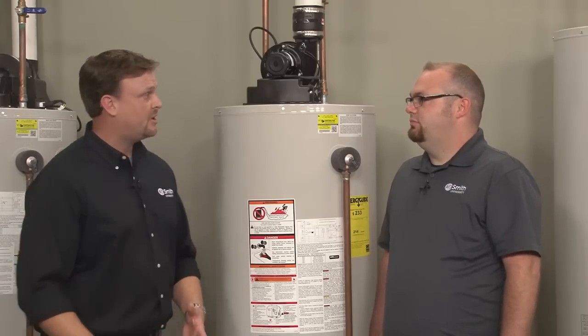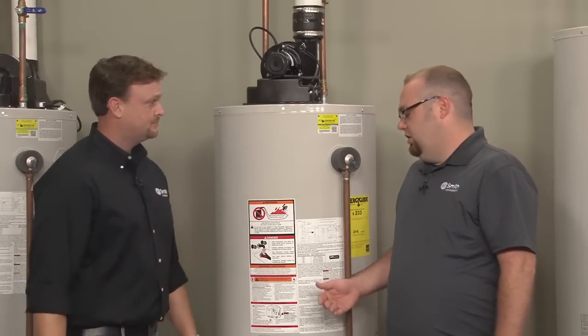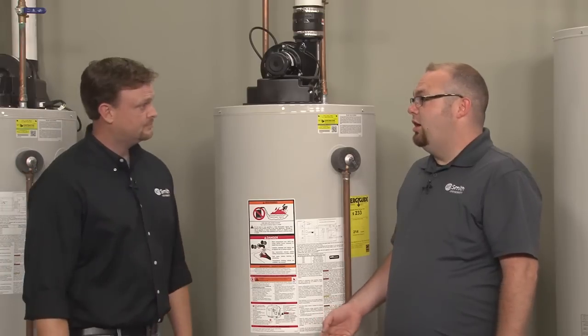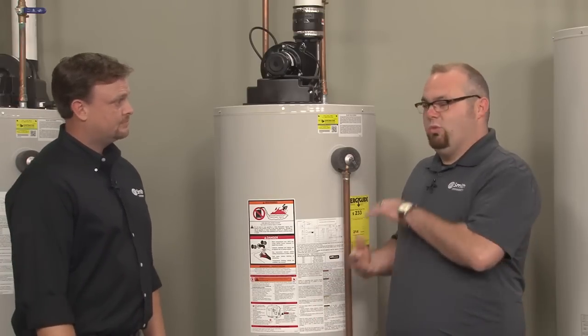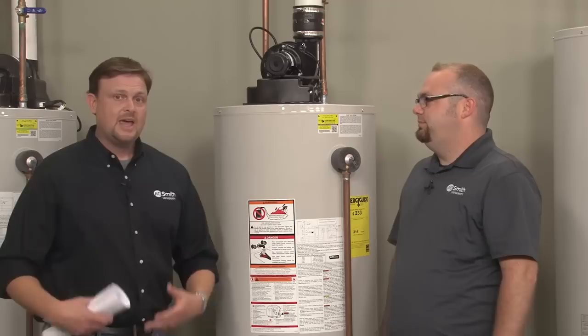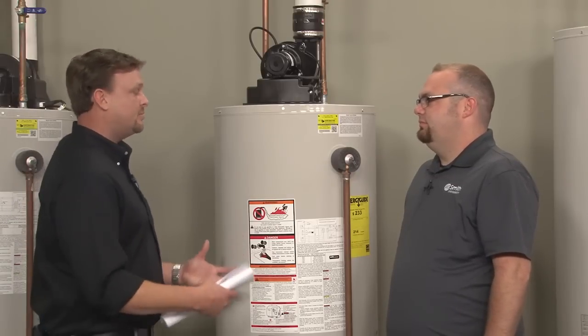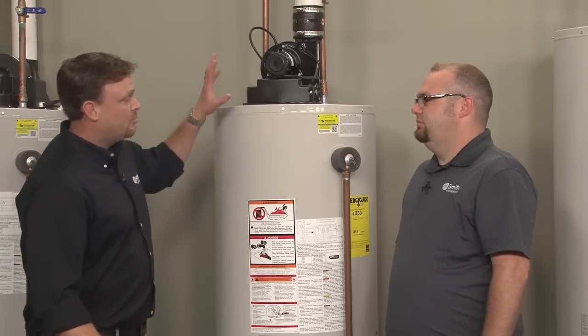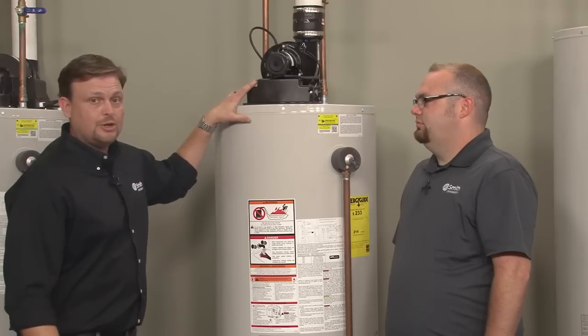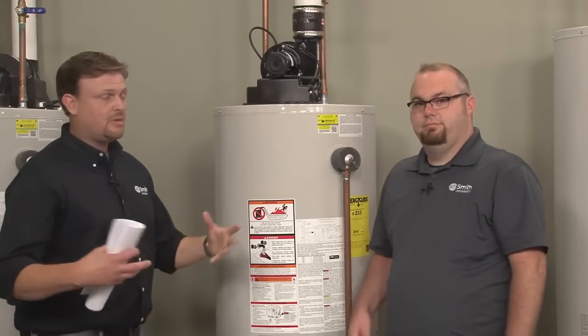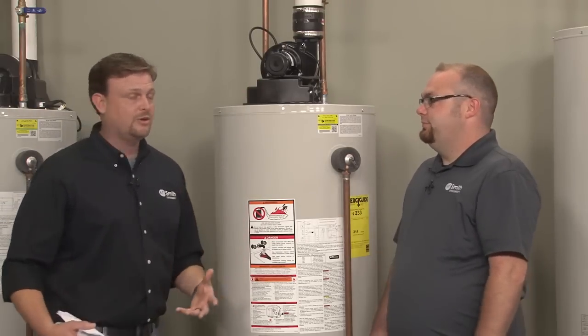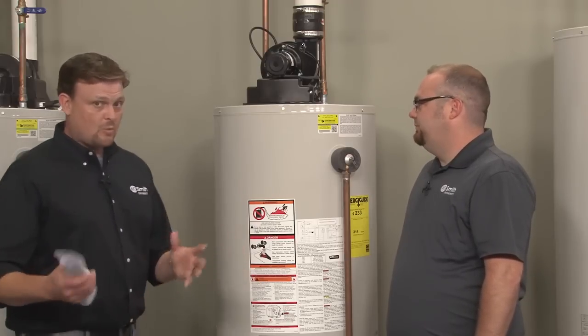Once it sees the flame, it just starts heating the water. Once it proves the flame, it's going to heat water unless it loses the flame or a switch opens or something like that. Then it'll come up to temperature, and the burner goes off. Your blower continues to run for a little while to get the combustion products out, and then the water heater goes into standby. Correct. So one more time, real quick.